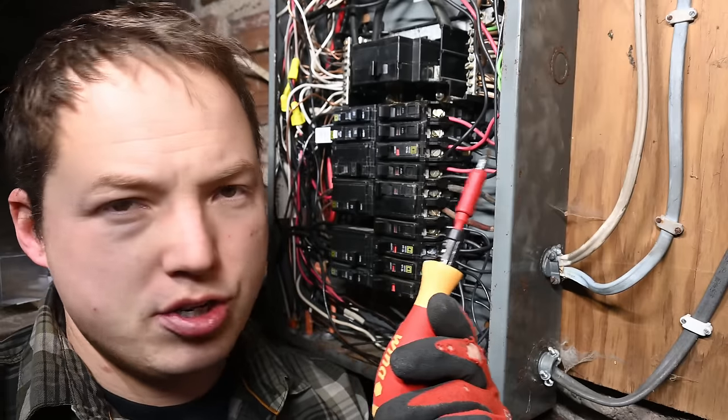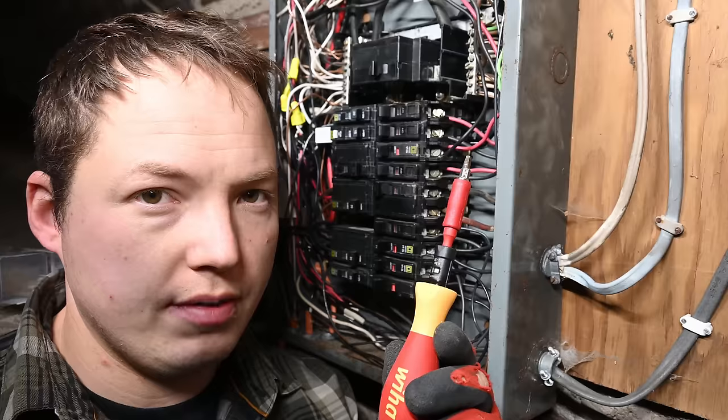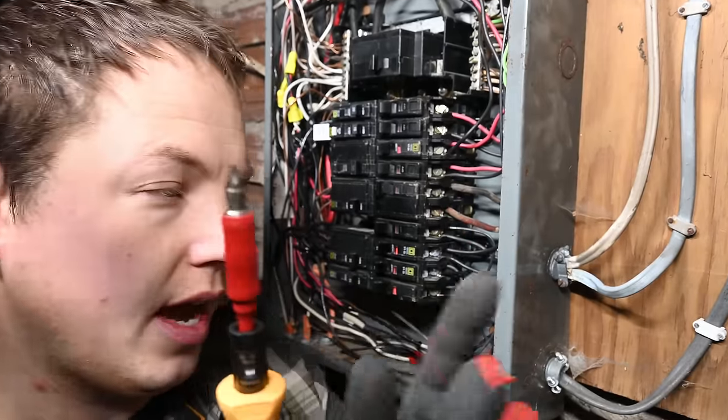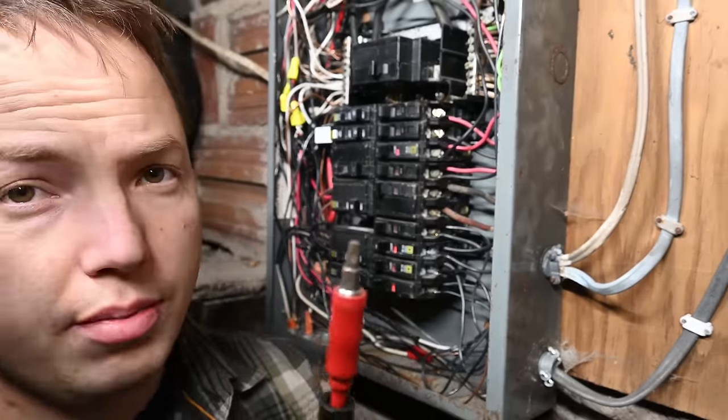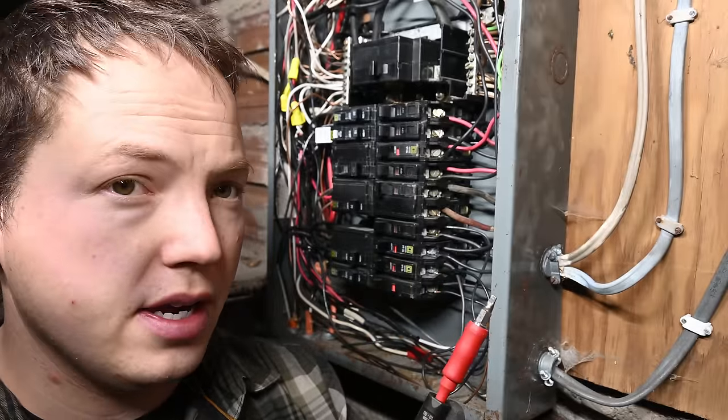In this video, I'm taking my torque screwdriver and going through and just checking connections that were already previously made. I'm just going to be checking the ones that have this proper bit connection at the moment. So there's only a few to do, but let's just see if the torque setting was already correct or if it actually needed to be increased.